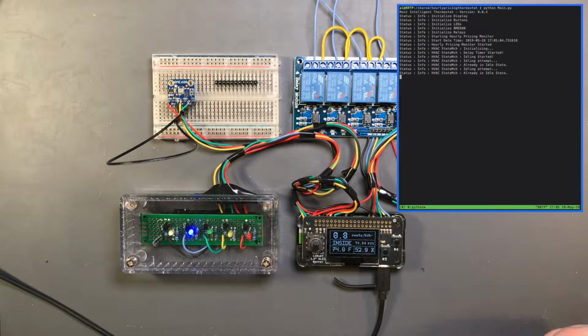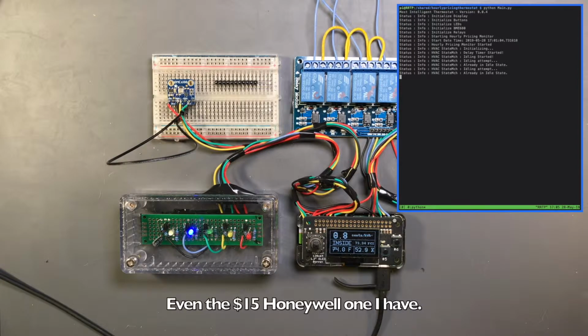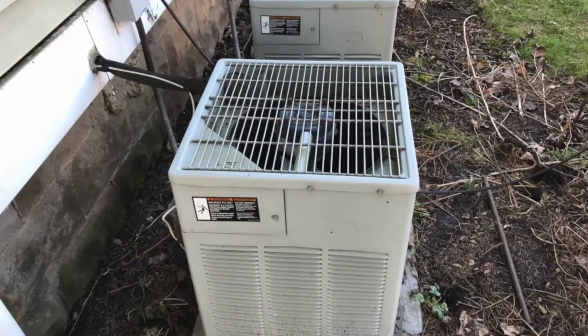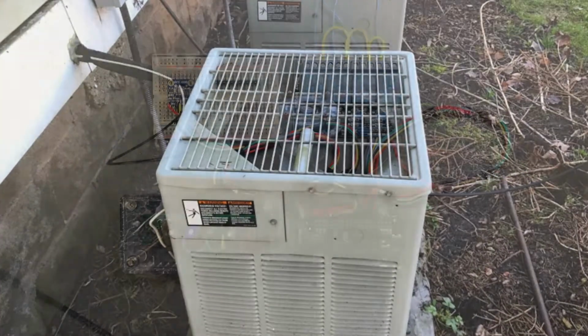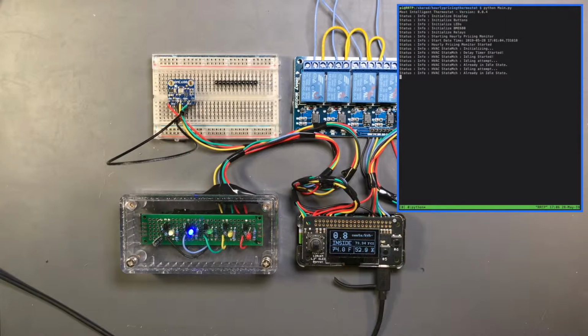Why does it do that? It is a feature that digital thermostats incorporate to protect the compressor on the outdoor unit, on your outdoor air conditioning unit. Why? Because after the air conditioner has run, the compressor and all of the high pressure side lines are at very high pressure. And if you shut off the system and then immediately try to turn it back on again, the compressor has to work really hard because there's so much pressure against it to start operating again.